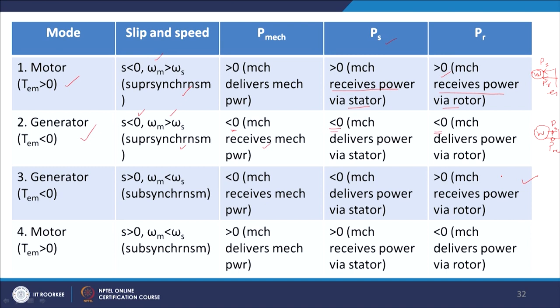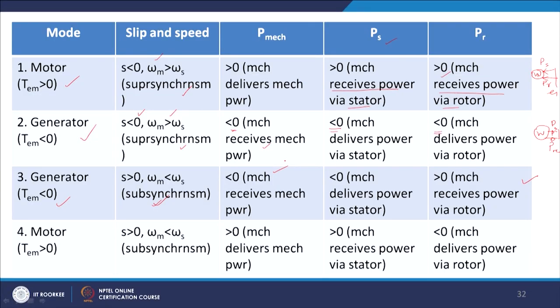The third mode is the generating mode at sub-synchronous speed, where TEM is less than 0 and the rotor speed is below the synchronous speed — known as sub-synchronous speed. Here P_mechanical is less than 0, meaning it receives mechanical power. PS is less than 0, meaning it delivers power via the stator. However, PR is greater than 0, meaning it receives power via the rotor from the grid. That is why it is called a doubly fed induction generator — power can be extracted from the grid or sent to the grid in a bidirectional manner.